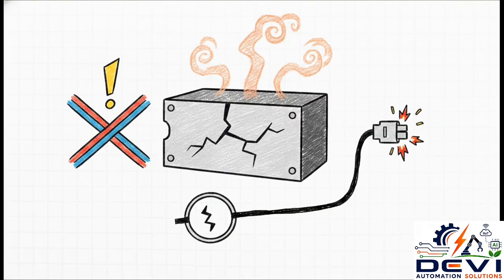Finally, Section 6, Common Mistakes to Avoid. You really need to watch out for these absolute project killers. Wrong phase connections or completely missing the earthing can be instantly catastrophic. Loose connections and using the wrong cable sizes, massive fire hazards. We already know poor ventilation will slowly cook the drive's electronics. And routing control and power cables together, well, that's going to give you phantom faults that will take weeks to troubleshoot. And of course, entering incorrect parameters or mismatched motor ratings means your VFD just can't properly protect the motor. A single error here ruins the entire setup.